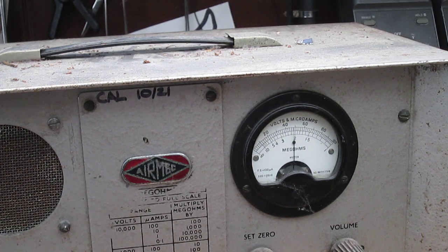Right, so let's say that's 5 kilovolts, and that is reading 2. Where are we? We're on the 1, and we're on there, so 2 times 10,000 mega ohms, 20,000 mega ohms. Put it to that one and it's just jumped straight over. Right, and that's reading good. I'm going to go all the way over. That's reading, that's 10 kilovolts.